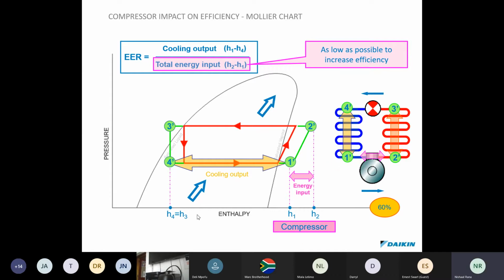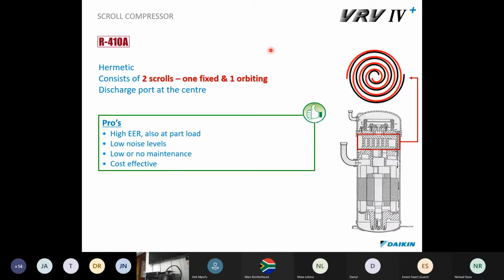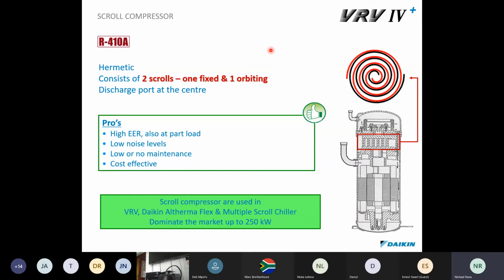So what are we trying to say? We're trying to say that our compressor is highly efficient, and I'll show you why in the slides to come. So our compressor is highly efficient, therefore giving you the best possible EER. So we have our scroll compressors, hermetic. They consist of 2 scrolls, one fixed, one orbiting, and the discharge port at the center. I'll show you a more detailed diagram of this now. So what are the pros? Obviously you can achieve a high EER, also at part load, because our compressors are fully inverter. The low noise levels.